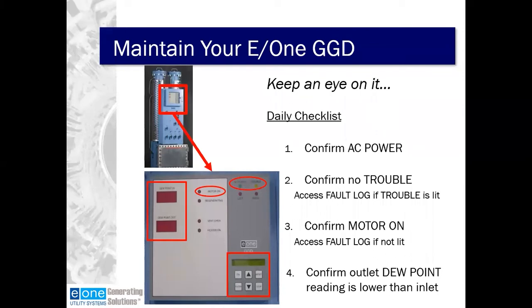The upper left-hand corner, again, has the inlet and outlet dew point measurements, and these are reported in degrees centigrade. Again, we want to make sure that the outlet dew point is reading a lower number than the inlet dew point, ensuring that we have a reduction in dew point as the gas is flowing through our generator gas dryer. And in the lower right-hand corner, again, we're identifying the multifunction LCD display area. That's where the fault log would be accessed, as noted in your software manual, to provide that information to us for troubleshooting.